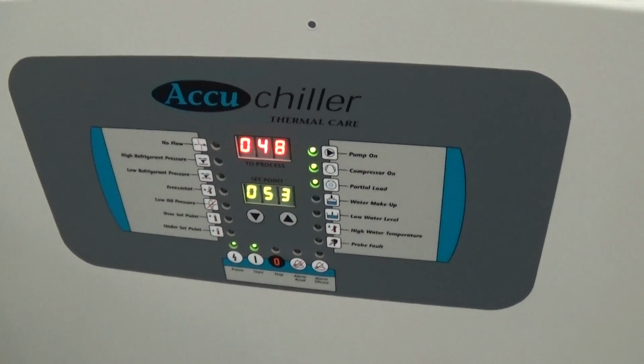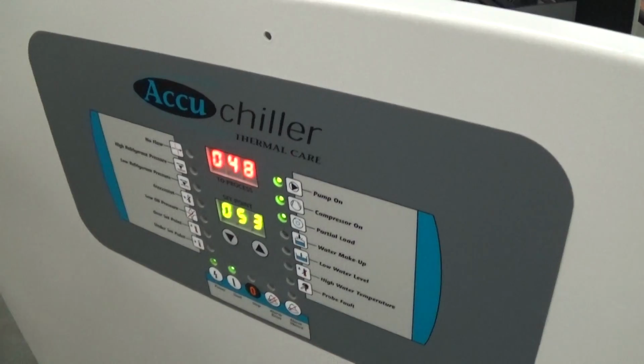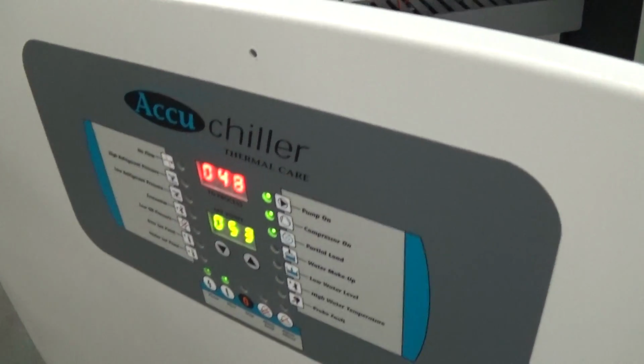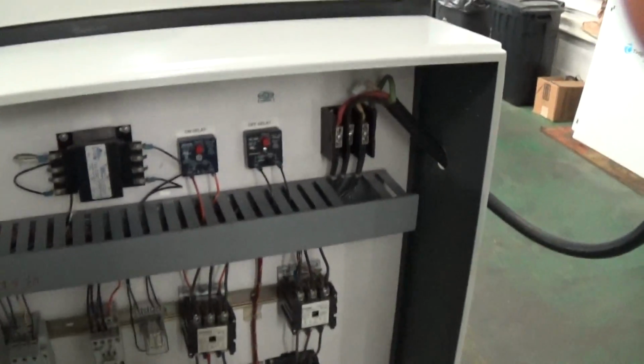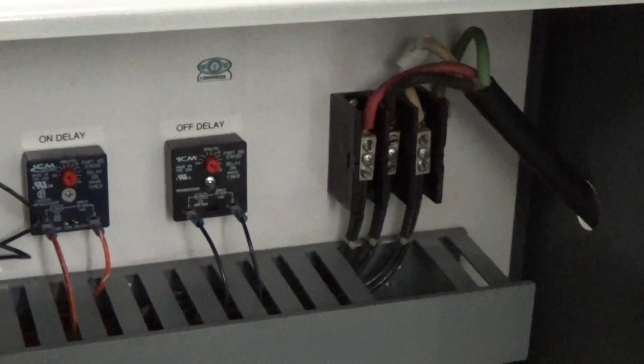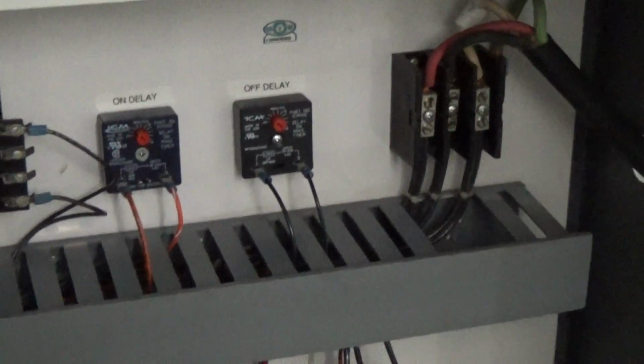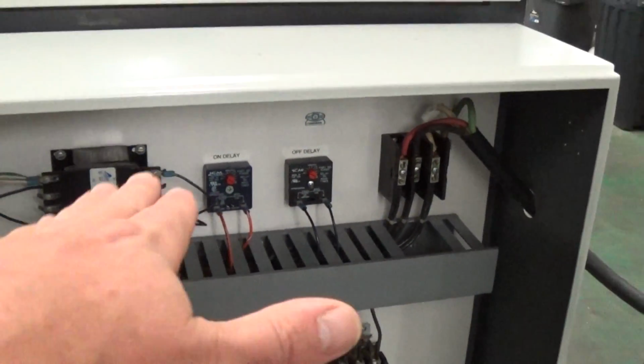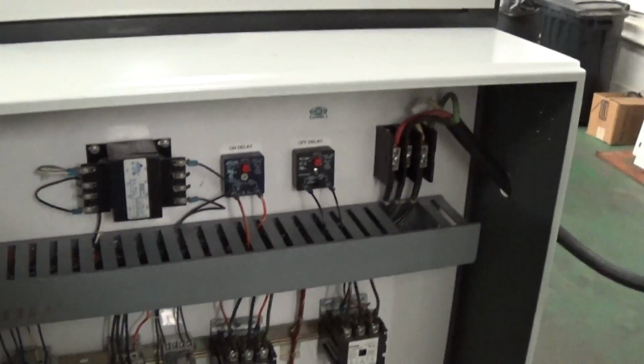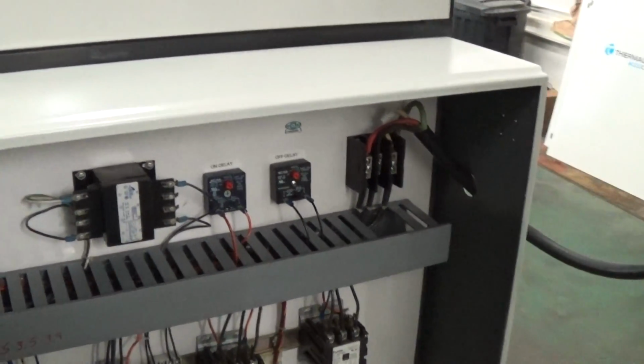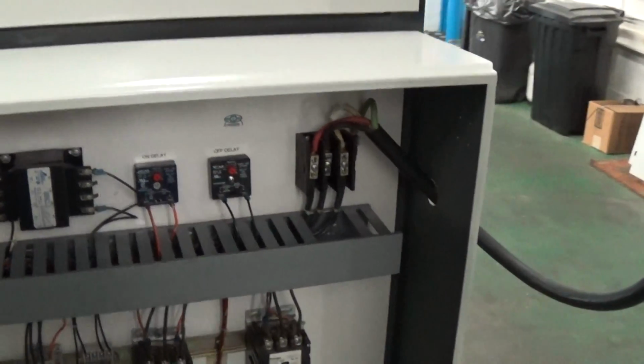So right now it's hot gassing a little bit. And then along with that hot gas, our off delay on one of the compressors is actually kicking in a little bit too. All this synchronizing between the on and off delay, that'll be fine-tuned by you, especially when you have a bigger load.